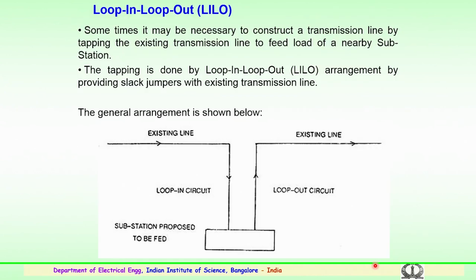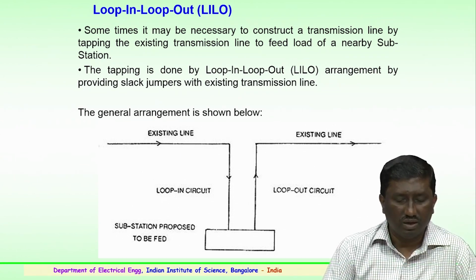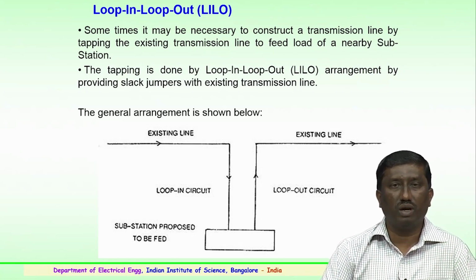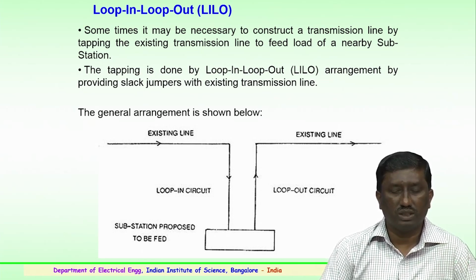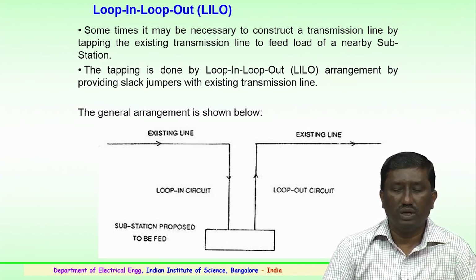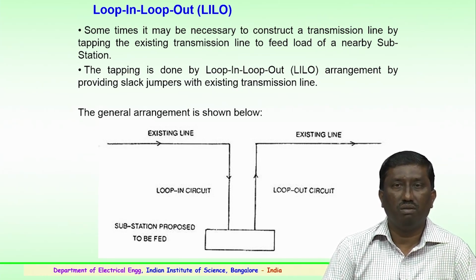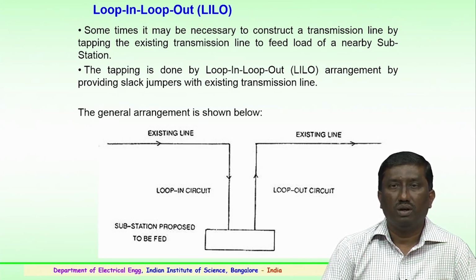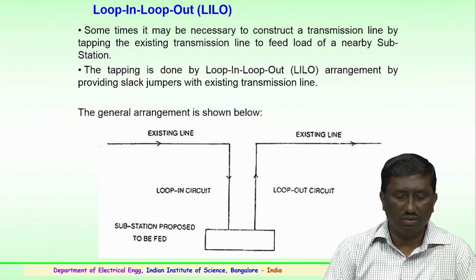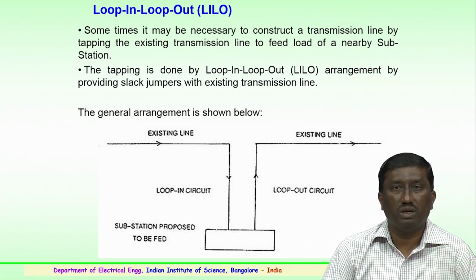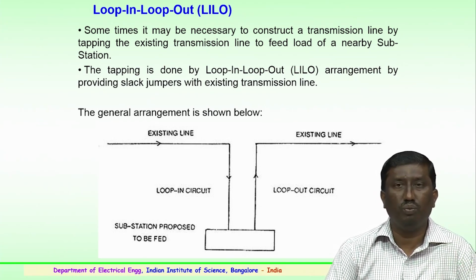transmission system. So, before going in for the uprating or upgradation of the existing conductors, we will find out some important aspects: how it is practically done and what the necessity is before the uprating or upgradation of the conductor is done. Sometimes it may be necessary to construct a transmission line by tapping the existing transmission line, which is to feed load, say, for a nearby substation or any other equivalent utility. The tapping of this transmission line is done by a loop in loop out arrangement, which is known as the LILO arrangement.